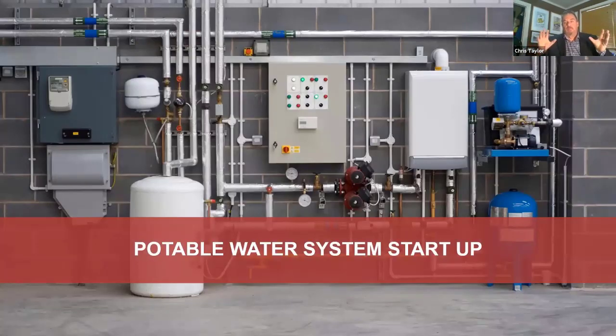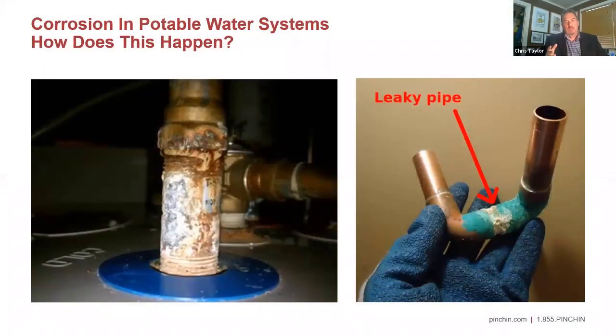On the potable water side, and again, I'll talk about potable water, but I'm including any sort of water feature type environment, it's the same kind of thing. And Steve alluded to this, but I'll give you some experience from some of the things that we found over the last year. In the lower mainland, one of the things that we found over years of water testing, originally for lead and now for starting up of buildings, is that the water supply seems to be slightly acidic. So from the municipal water supplies, you have water that's in the pH of around 6 range. And so if that acidic water has been sitting stagnant, not only do you have the Legionella biofilm kind of concern, but now you've got a situation where there may have been corrosion occurring. And enough corrosion leads to pinhole leaks.